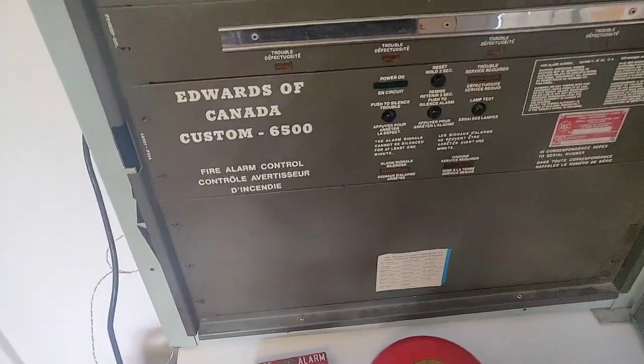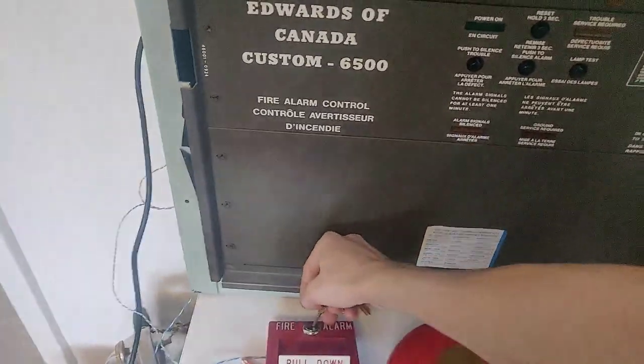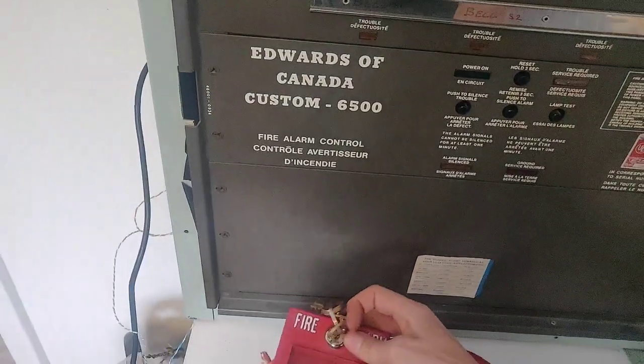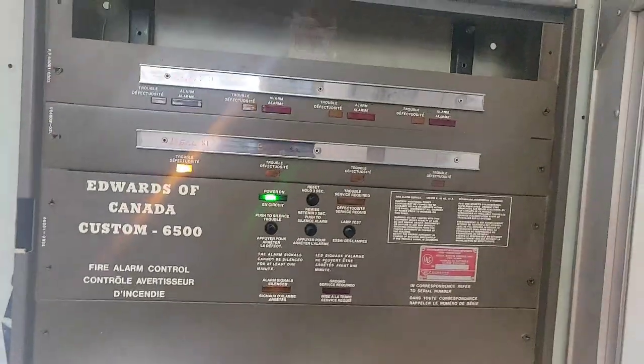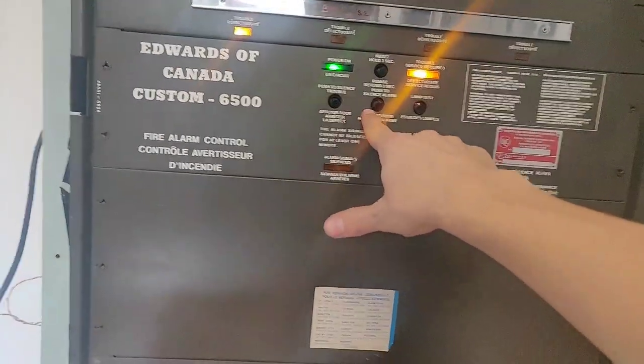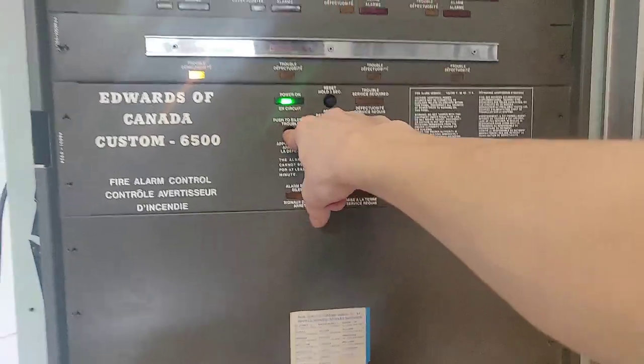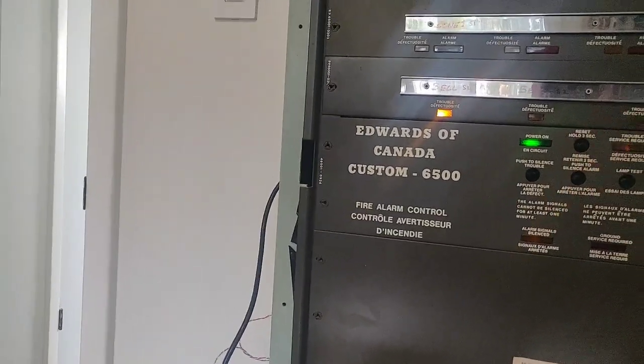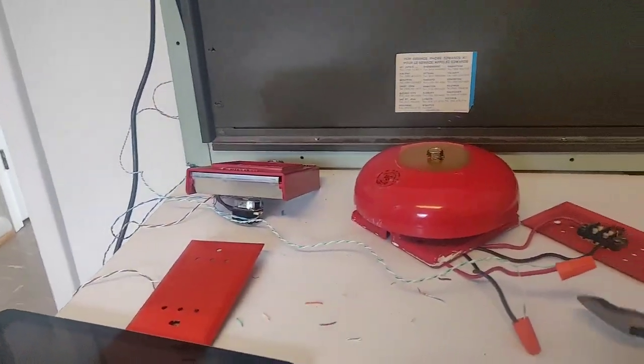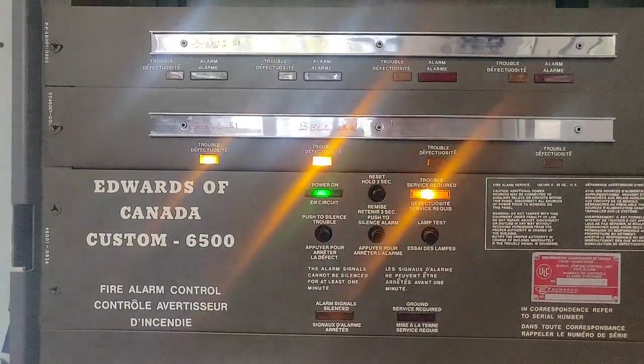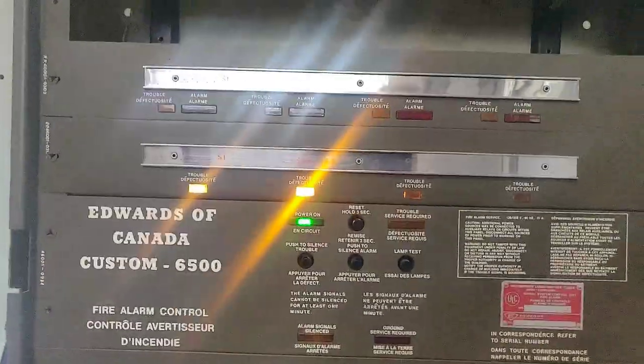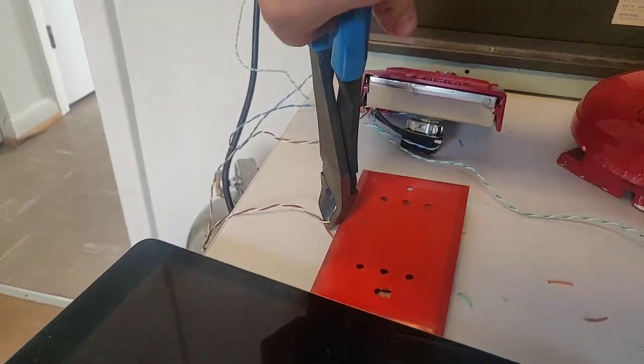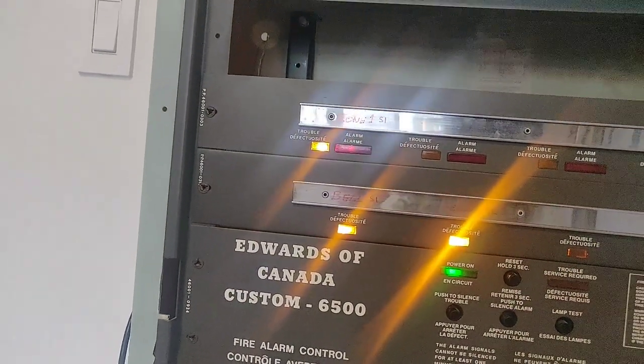So I shut off the power to the panel because I can't get it to reset with the button. I have to do some repair. Now that the pull station is reset, we can bring back power and we are back to a normal non-alarm state. So to demonstrate again, once again, our trouble circuit, I've got our wire cutters. See, I cut the bell circuit. We have a trouble. Now let's go to our pull station. And there we have a trouble on that loop, so that's all working.